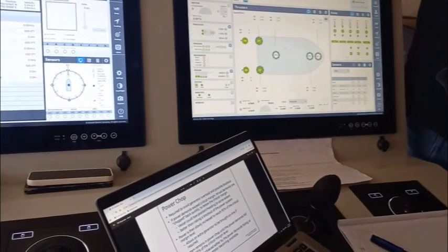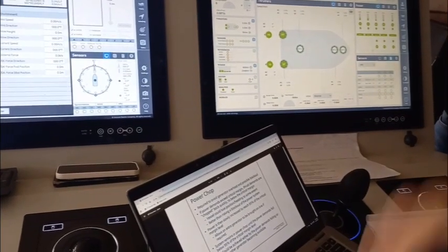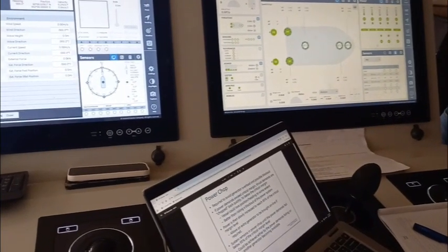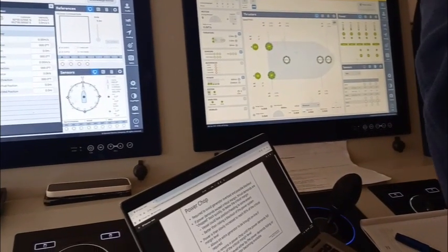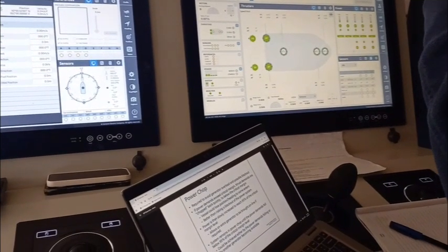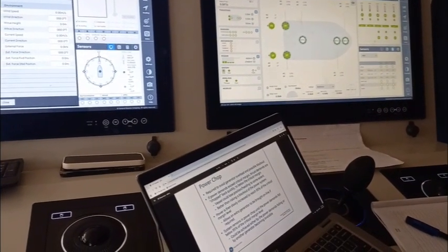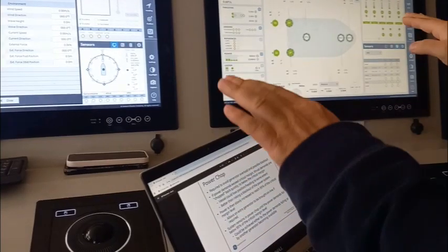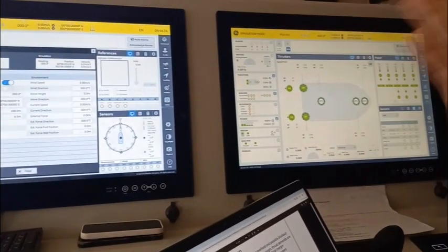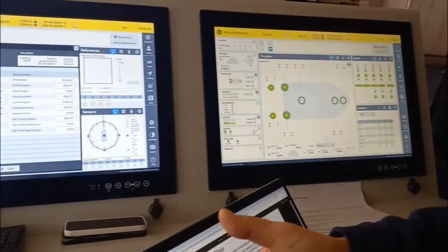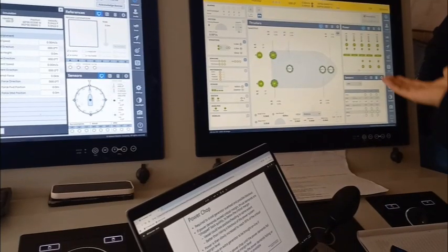Increase the generator number from 2 to 3 or even more to make sure. That's an operational experience. If you find the generator load is more than 50%, that's a risk line. I have to stop the load immediately. You should never allow the power to go above 95. But this is a protection line in the backwards direction, to make sure you're not blacking out, even though you have the diver there. If you forgot to get the diver back or forgot to increase the generator.